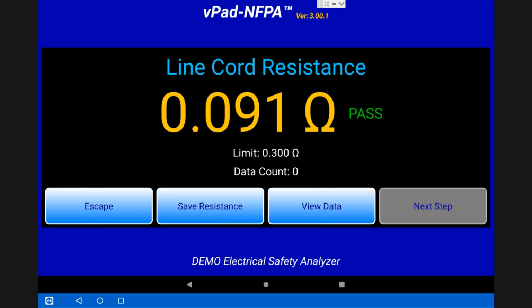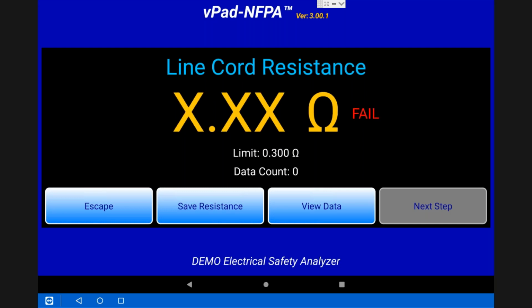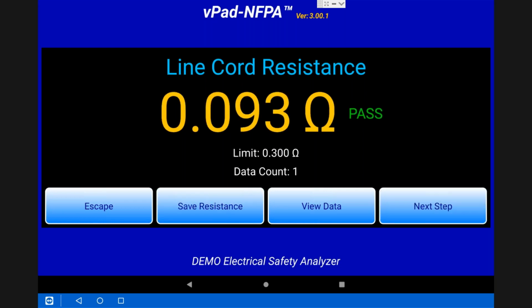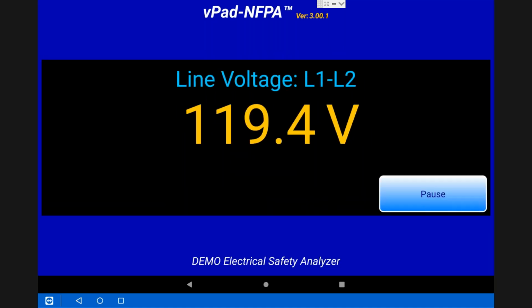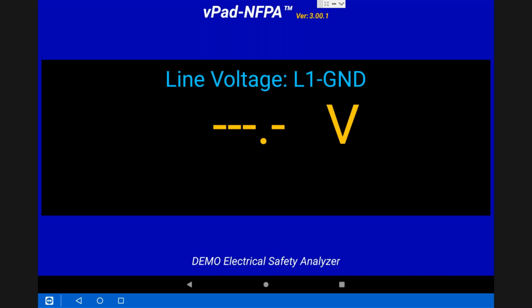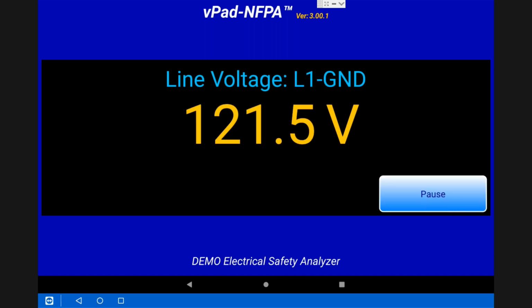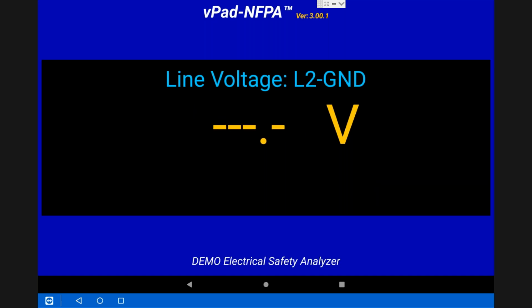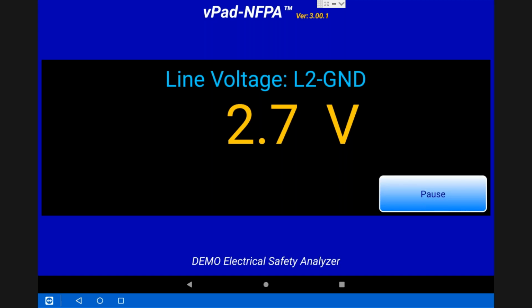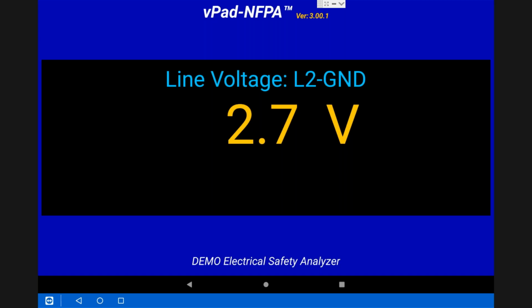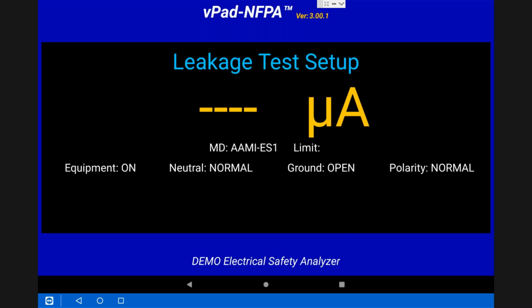So currently I'm at my line cord resistance. I can flex my power cord at the wall end and at the equipment end. When I'm ready to save my resistance value, I can hit save resistance and next step. From here forward, it's going to start to take automatic measurements in the off state, and it's going to indicate when the power is going to come back on to the unit.